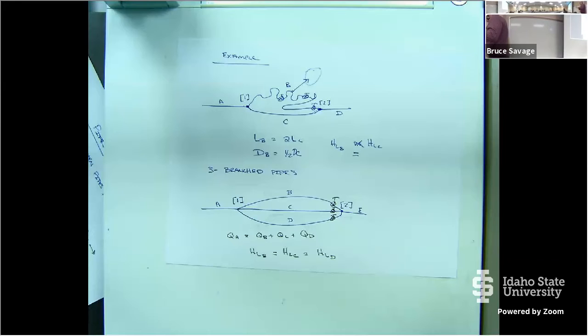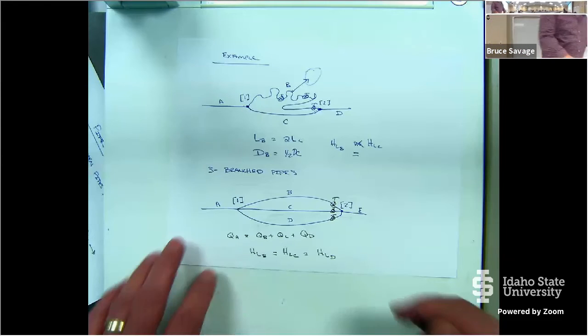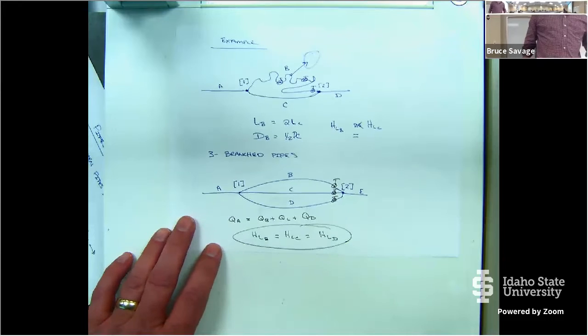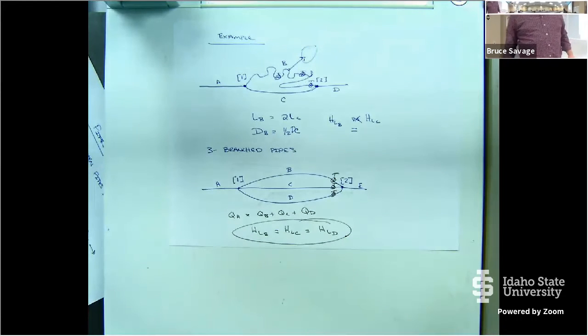The head loss itself will not stay the same, but the head loss across all 3 of those pipes is going to be equal. So that's the point here. If I change something in the system, the head loss does not stay the same, but they do stay equivalent.